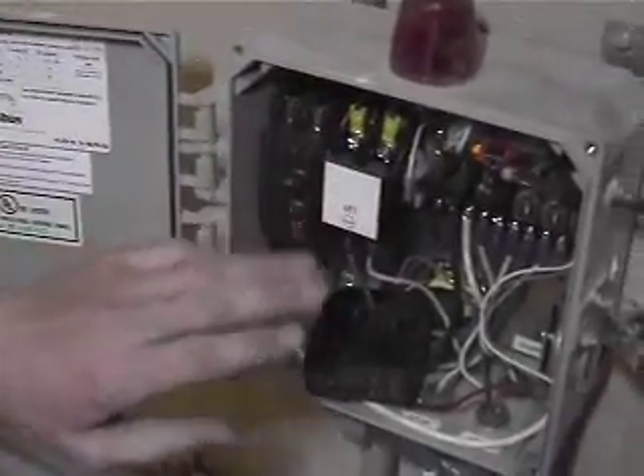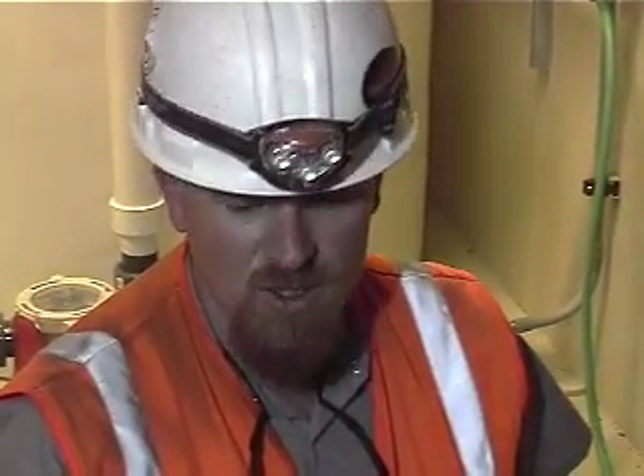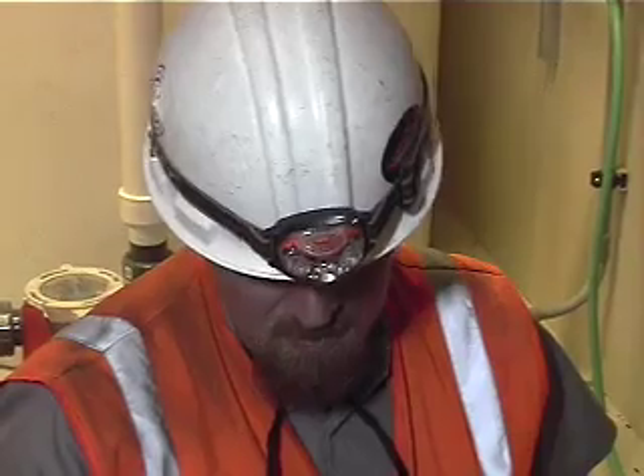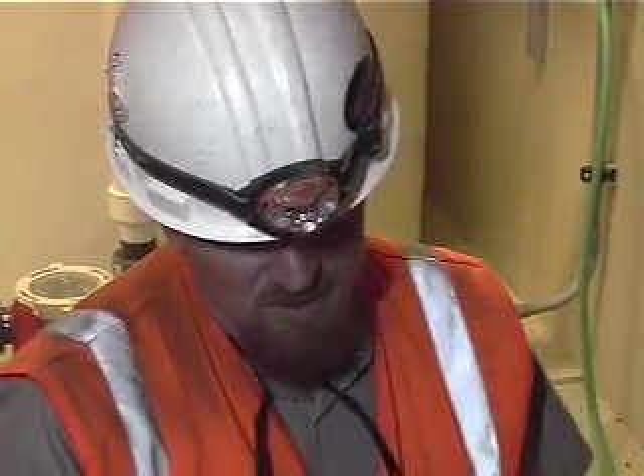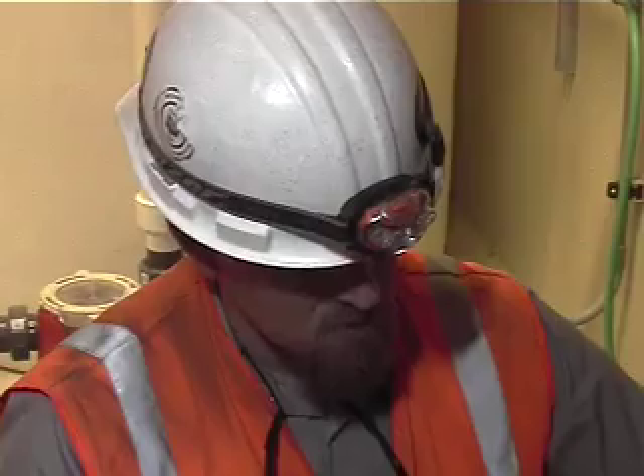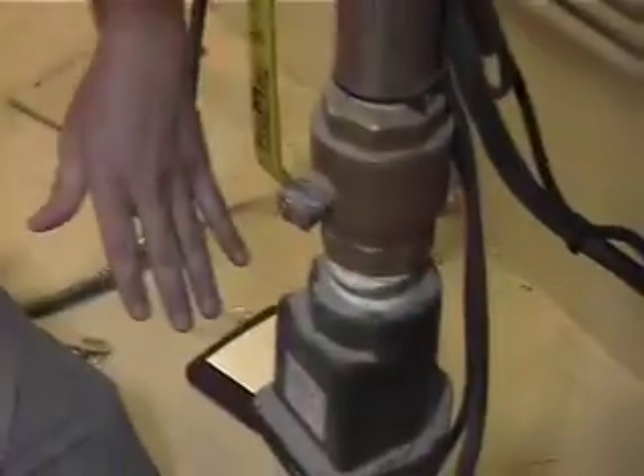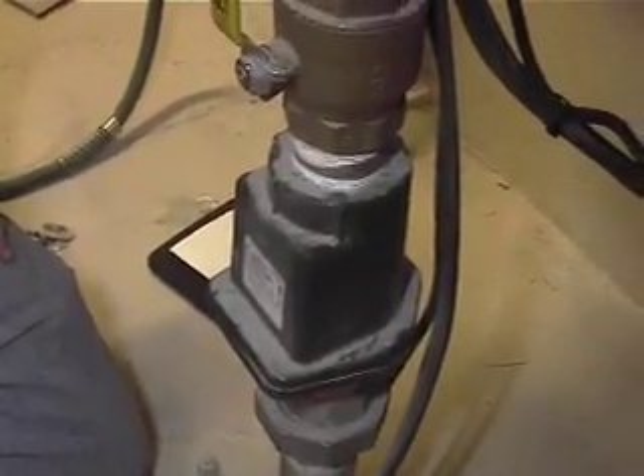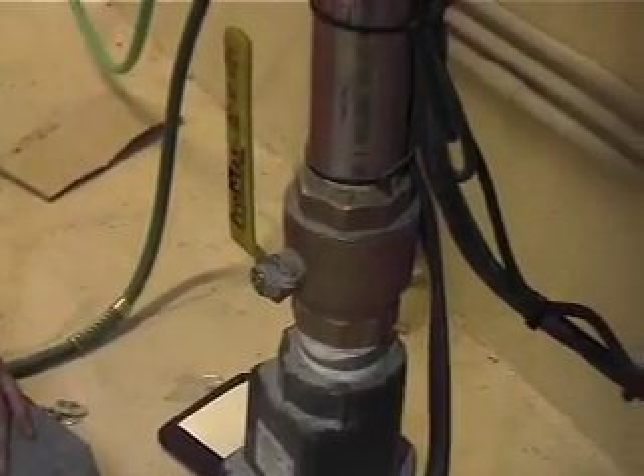You would need to occasionally check your contactor, make sure that you're not seeing any arcing. My guess is that's not going to happen for quite some time. This shouldn't be running very often, if at all. It's just going to be picking up stuff from the floor drain, and then once that fills up, sets that float, it will come on, run through this system, push it out. There's a check valve here to prevent the fluid from coming back down, and shut off. That's about it.